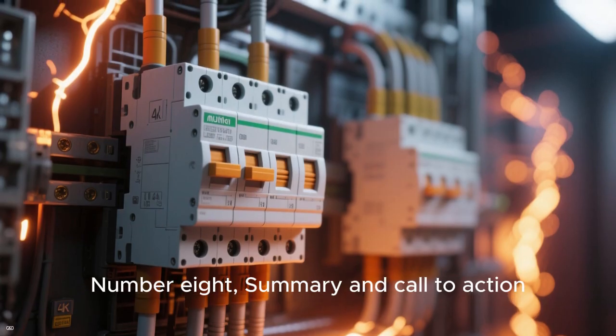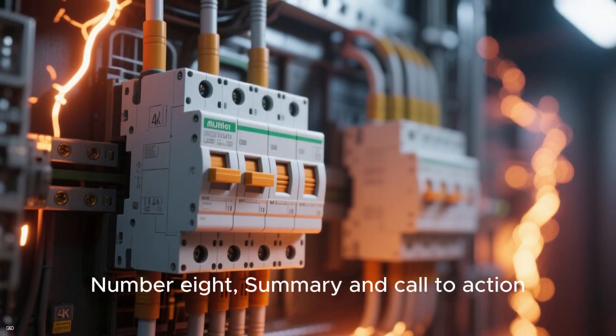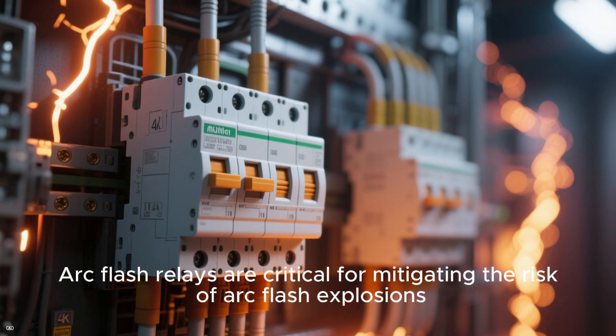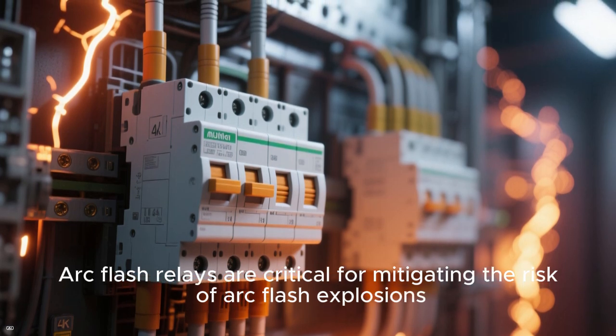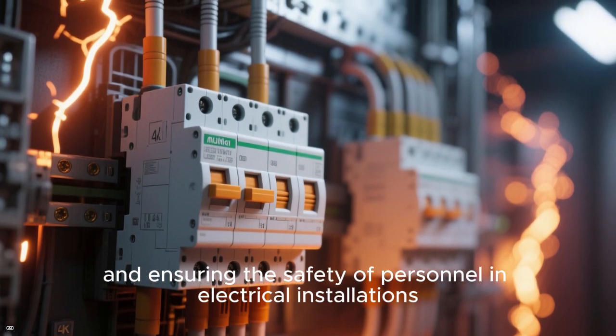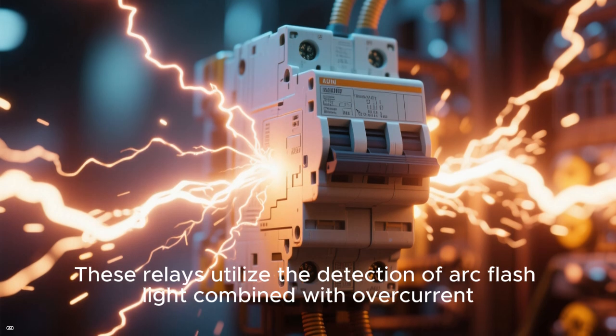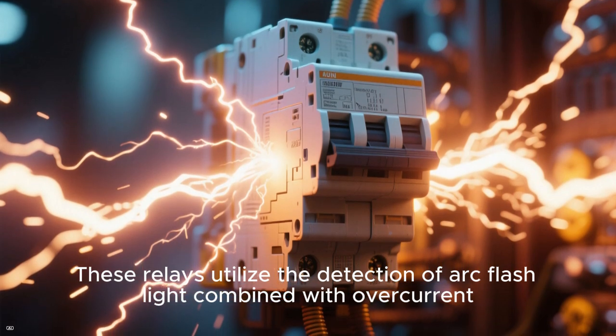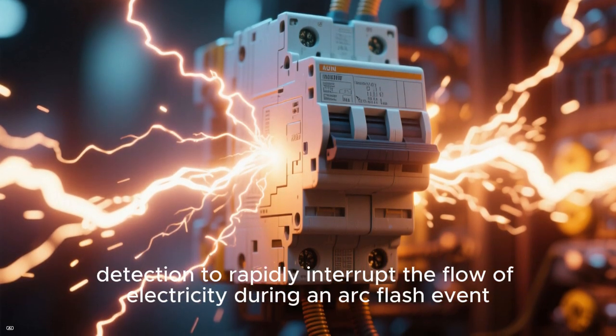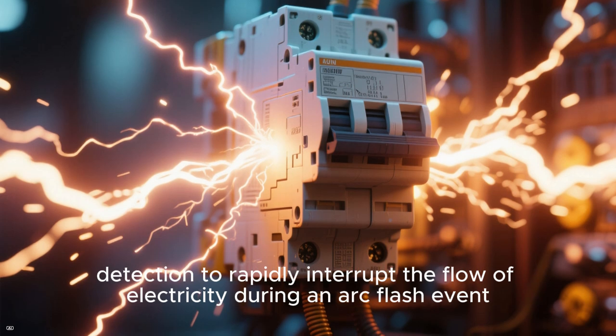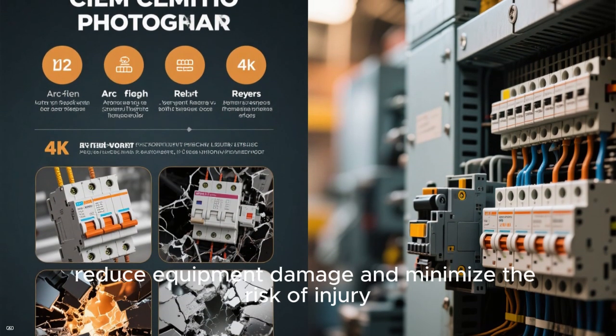Number 8, summary and call to action. Arc flash relays are critical for mitigating the risk of arc flash explosions and ensuring the safety of personnel in electrical installations. These relays utilize the detection of arc flash light combined with current detection to rapidly interrupt the flow of electricity during an arc flash event. This action helps to limit the incident energy, reduce equipment damage, and minimize the risk of injury.